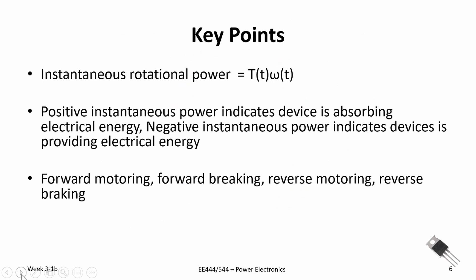Let's touch on the key points. We went over instantaneous rotational power, which equals instantaneous torque times instantaneous angular velocity. Positive instantaneous power indicates the device is absorbing electrical energy; negative instantaneous power indicates the device is providing electrical energy — analogous to passive sign convention for electrical devices. Finally we looked at the four quadrants of motor operation: forward motoring, forward braking, reverse motoring, and reverse braking. That's important as you design a four-quadrant motor driver — you'll need to consider how you handle current, which is proportional to torque, and the voltage applied to the armature.